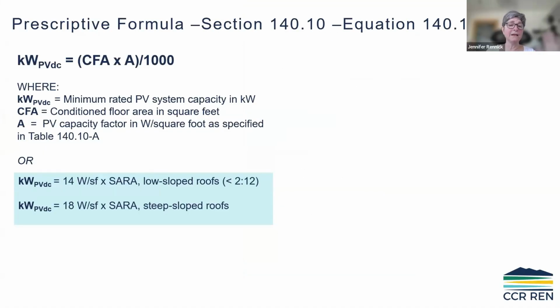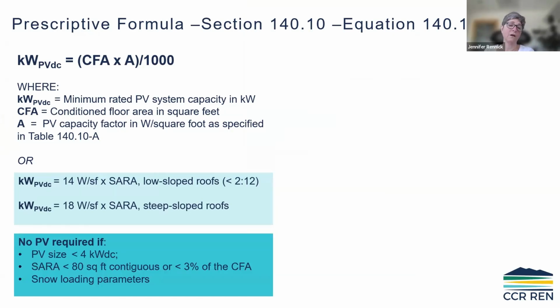Just to give you an idea, for the architects on the call, if you go to section 140.10, there's an equation you follow. It's based on conditioned floor area, times A, which is a factor for your PV, and then you divide that by 1,000. It's also based on your square footage of solar accessible roof area. And then if your PV system size is very small, you don't have to install the PV.